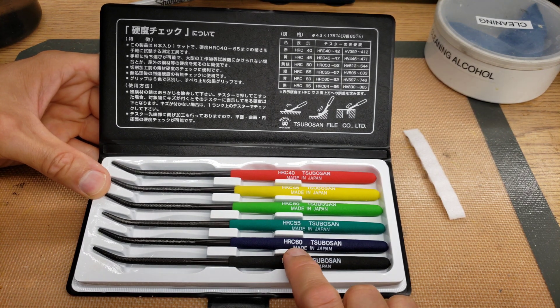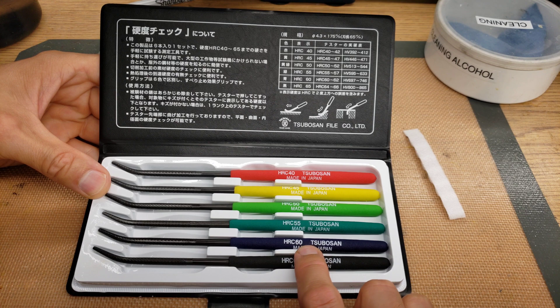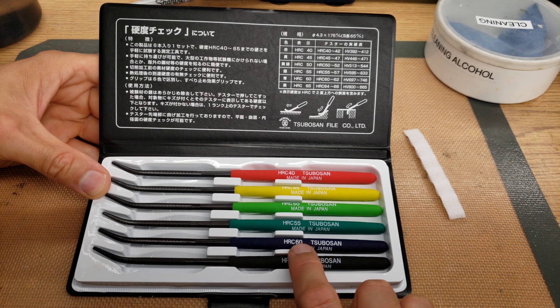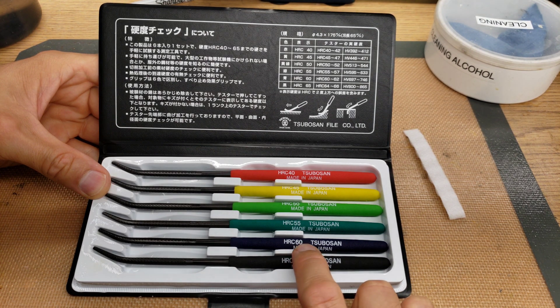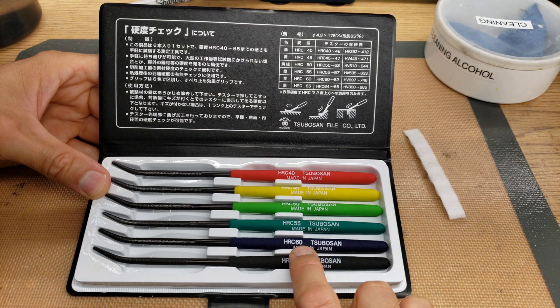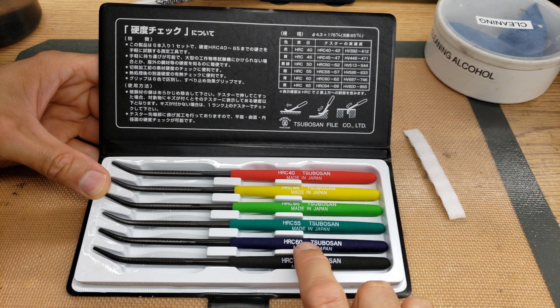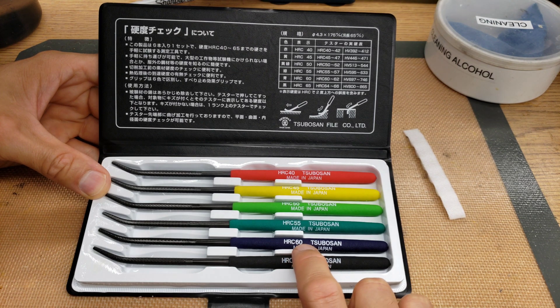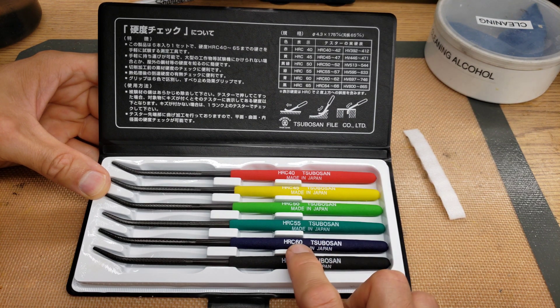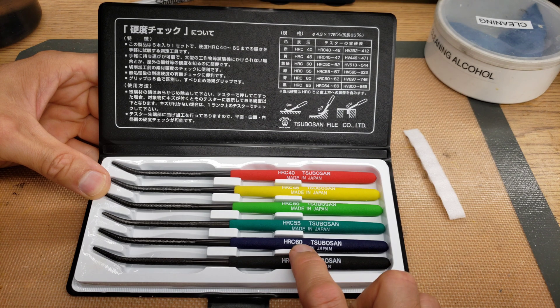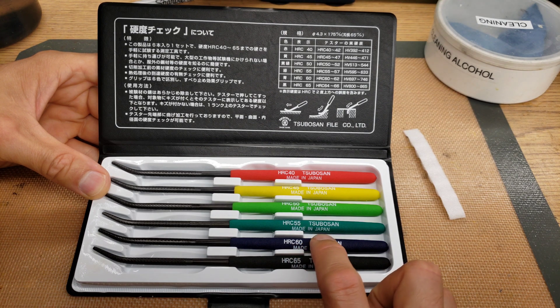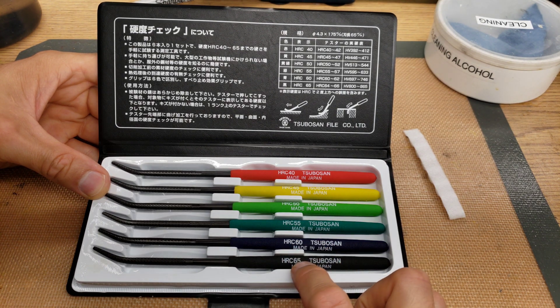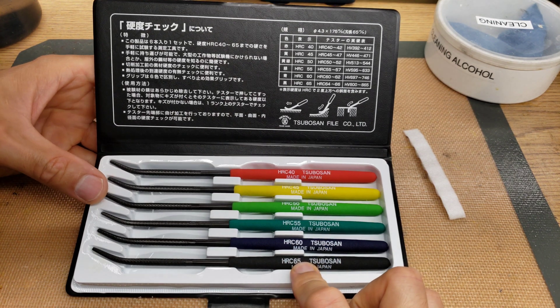So then you go down to the blue. If the blue marks the material, then you know that the material is softer than HRC-60. If the blue skips off the material, like if it doesn't mark it, then you know that the material is somewhere between 60 and 65 HRC.